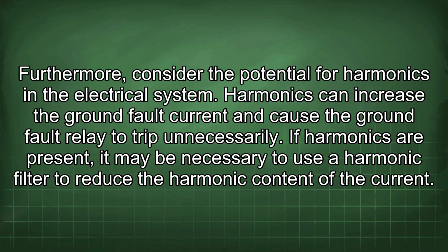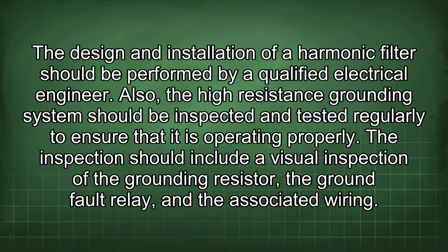Furthermore, consider the potential for harmonics in the electrical system. Harmonics can increase the ground fault current and cause the ground fault relay to trip unnecessarily. If harmonics are present, it may be necessary to use a harmonic filter to reduce the harmonic content of the current. The design and installation of a harmonic filter should be performed by a qualified electrical engineer.